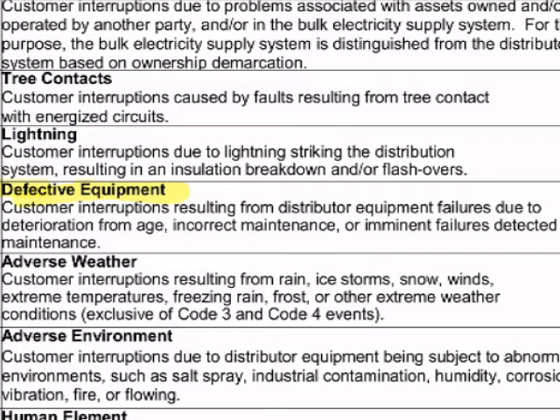Defective equipment is OEB speak for my stuff broke. Could be old stuff, could be new stuff, but a piece of equipment that was supposed to work failed. Could be a pole that broke, could be an insulator that cracked, could be any number of things. But if the cause of the outage could be traced back to a piece of equipment that stopped doing what it was supposed to be doing, it gets categorized as defective equipment, regardless of the age of that equipment.